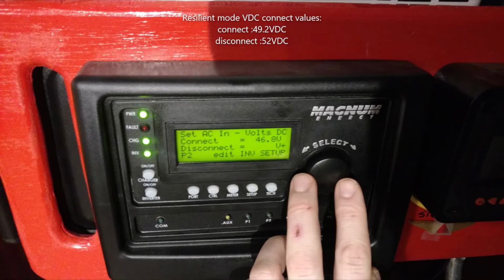I'm showing that to have lots of energy saved up in the battery, I need to increase the voltage levels so that its reserve power is saved in the battery. I move the connect voltage from 46.8 to 49.2 and the disconnect voltage from 48.8 to 52 volts for a 15 series lithium iron battery. In energy maximize mode, I have the battery go nearly dead every night, and in the morning switch to solar as soon as there's 1 kilowatt hour in it.